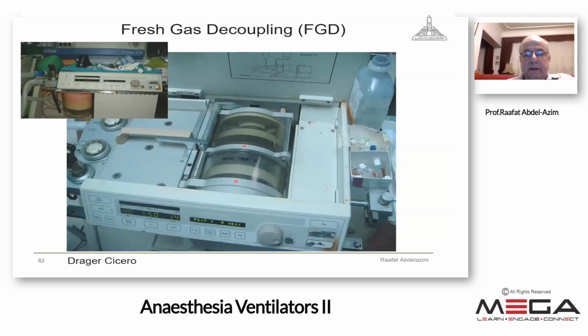In the Dräger Cicero or Primus or Fabius, we have what's called fresh gas decoupling. Fresh gas decoupling means separation of the relationship between the ventilation and the fresh gas flow, decoupling. By decoupling, two changes have been made in the ventilator. The first one, you can see here, as I displayed before. This is the Cicero ventilator. This is the cover here.